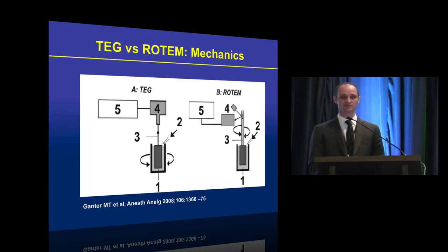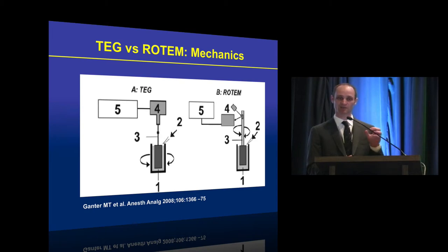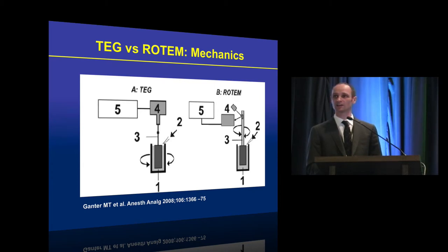With ROTEM, there are similarities but also subtle and important differences. You still place a blood sample in the cup, but instead of the cup rotating, it's the pin that rotates. When clot starts to form within the well, this affects torque on the pin, which is detected by an optical detector system, converting the signal into an electrical signal and producing a trace on the computer screen.